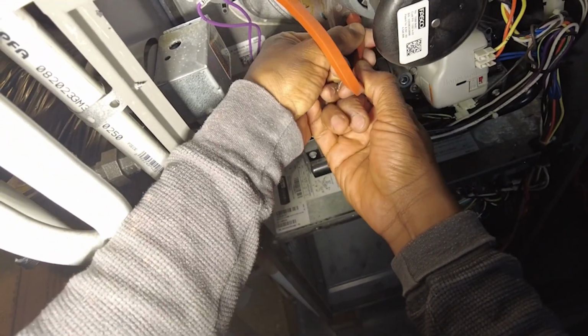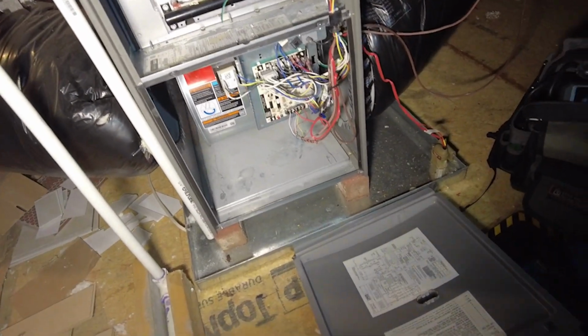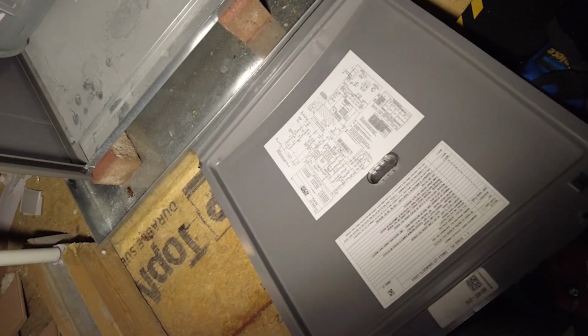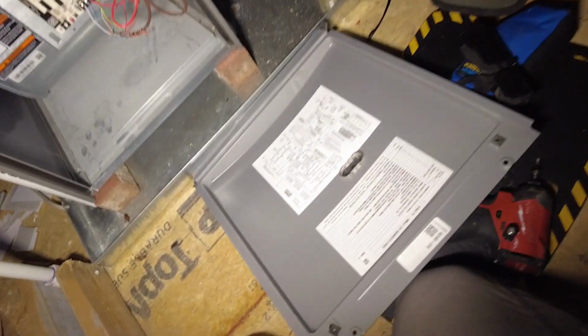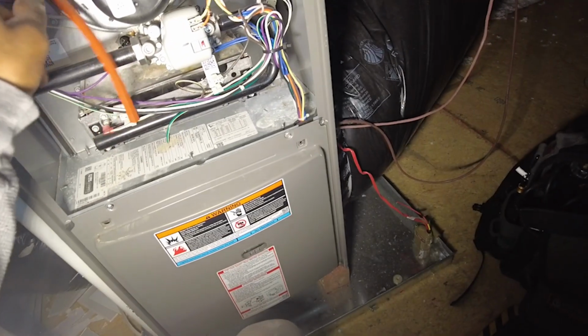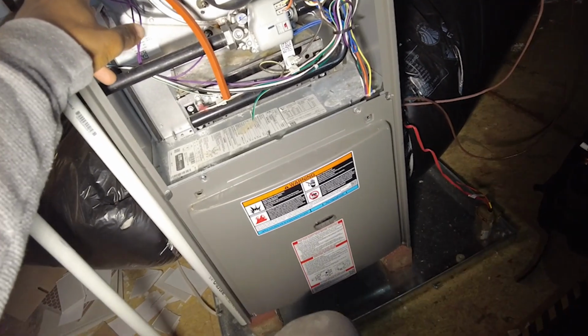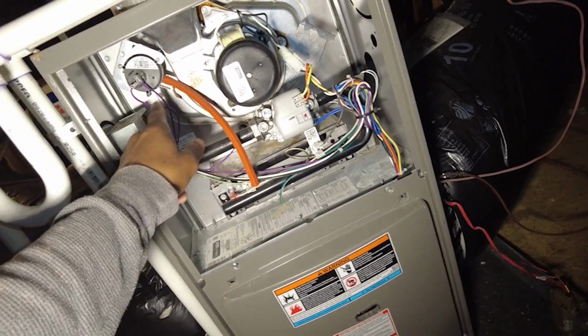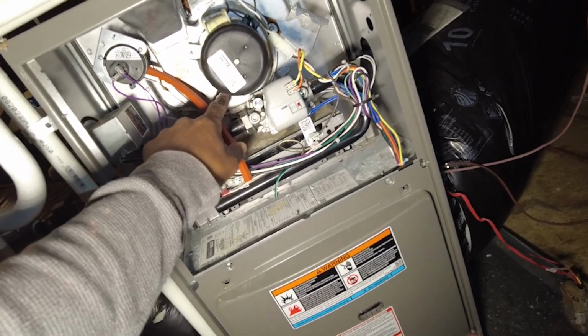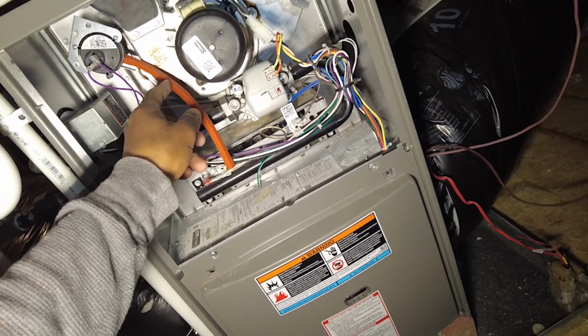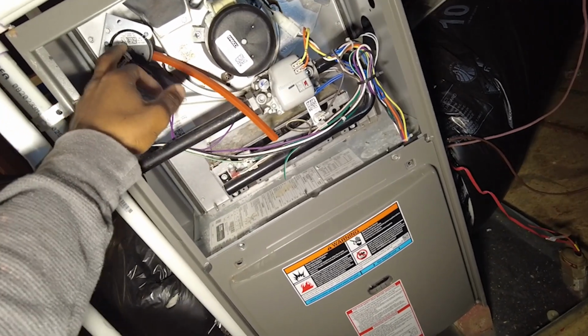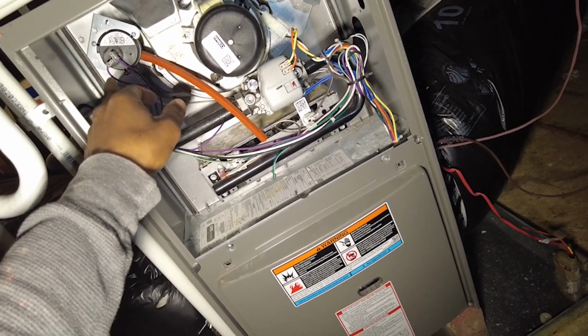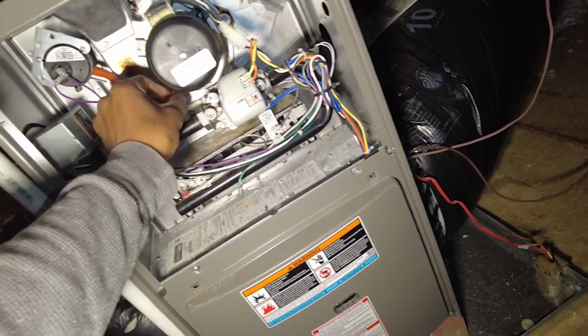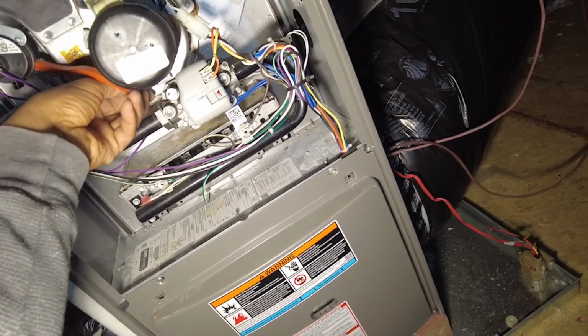But the reason that's coming off. Sweet. So you see there's a little port there. Now what I'm going to do with that, I usually keep a wire that'll fit in there, thermostat wire or something. If this gets blocked up, it's going to stop making negative pressure. See this pressure switch here? This is what they call a pressure switch, and that's going to be letting the furnace board know that this inducer is running. So if this hole gets clogged up, then essentially it's not going to pull in the diaphragm in this pressure switch in order to make contact in these two lines here to let the board know we got a draft inducer running. So that's pretty important to keep cleaned out.